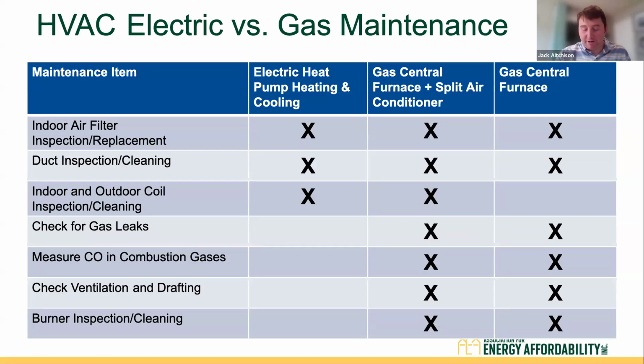So this is a pretty important slide here. This is HVAC electric versus gas maintenance. So starting off, electric heat pump and heating and cooling. Really, this is just illustrating the fact that when you have a heat pump that provides heating and cooling, and you have existing cooling in your building, you compare that to a mixed fuel building where you have a furnace and a split air conditioner. All of the things that you need to do to maintain your split air conditioner are the exact same things that you're going to need to do to maintain your heat pump. Just if you have a gas furnace, you're going to have to do additional things, which are to check for gas leaks, measure carbon monoxide and combustion gases, check ventilation drafting, and burner inspection and cleaning.